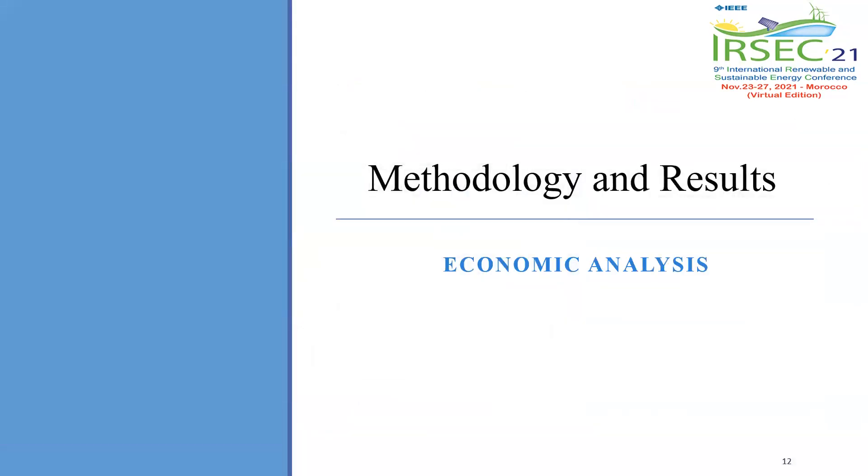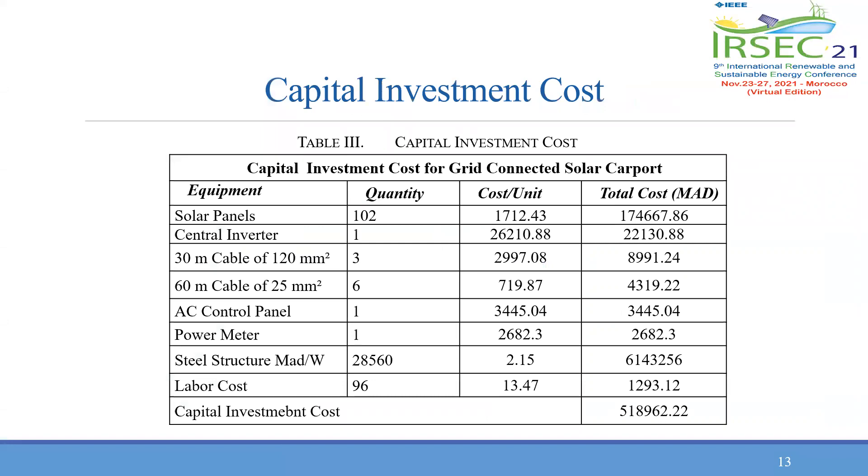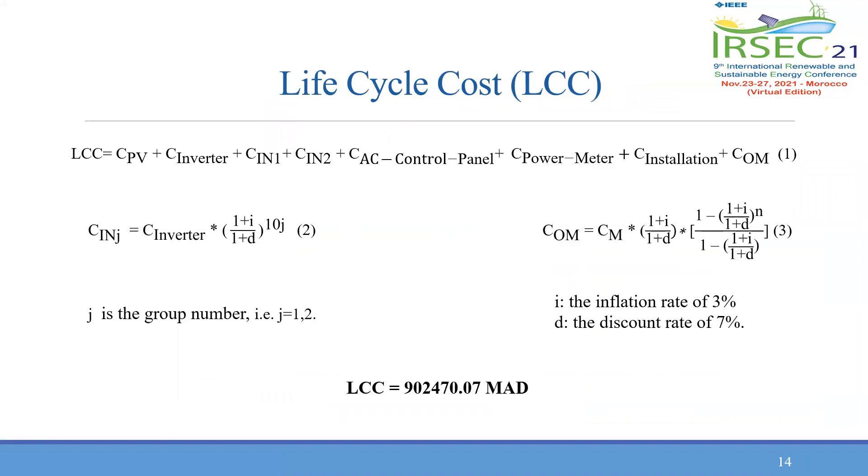For insight into the economic potentials of the system, an economic analysis was made. The capital investment is 518,000 Moroccan dirhams, as shown in the table on the slide. To assess the total cost of owning and operating the solar carport system, the life cycle cost is expressed with the first equation. The lifetime of the PV modules is 25 years, while for the inverter it is only 10 years; therefore, two extra groups of inverters should be purchased after 10 and 20 years. The life cycle cost is 902,470 Moroccan dirhams.